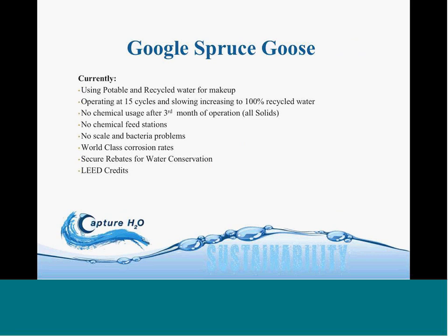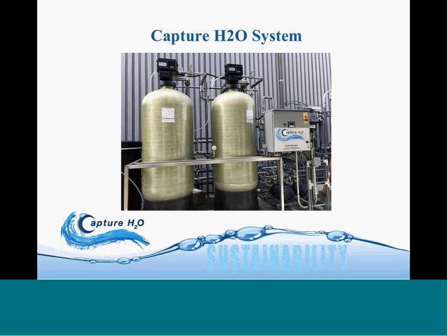After the third month of operation, we haven't used any chemicals. Typically, to get the metals passivated and everything lined out, we feed a little bit of silica in the beginning to get the passivation chemistry on the metal. But after we have that, we can eliminate that chemical. So right now they're not using any chemicals. They have no chemical feed stations. There's no scaling on any of the equipment. Bacteria levels are non-existent, the water is basically sterile, and the corrosion rates are really low. And again, they've gotten rebates and LEED credits for that project.